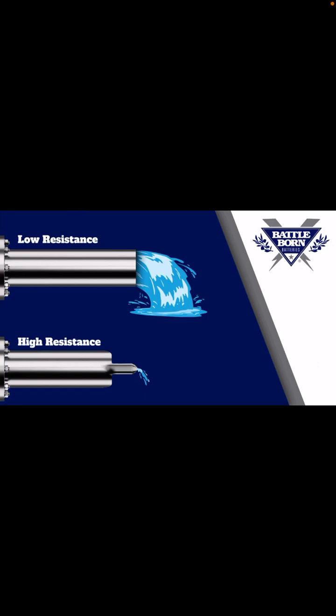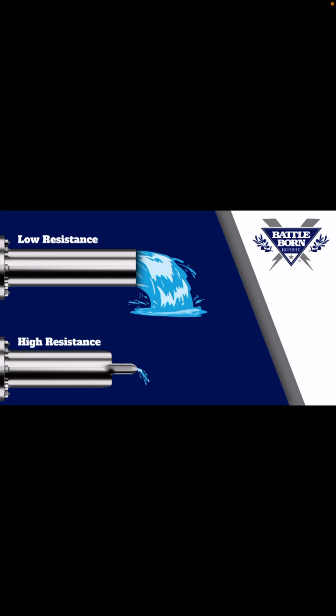One way that sometimes I test those things is I'll disconnect the switch and I'll check my resistance across the switch. Then I'll take the switch off and check the circuit, say it's going to a heating element. I'll check from the heating element all the way through to the wire and see what my resistance is. Then I'll slowly isolate it. I'll disconnect the heating element, disconnect the switch, and only check the wires going between them and check that resistance. And that just helps you troubleshoot sometimes. Usually you're going to find that with your eyes, you're going to find a loose connection or something. But sometimes it's not that simple, and you can use resistance to help you in troubleshooting. Find out where you're getting more resistance in the circuit and isolate it.